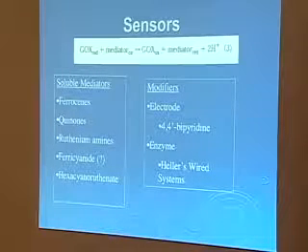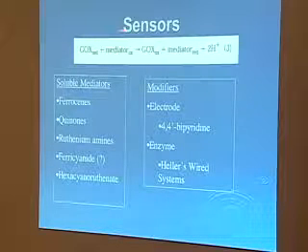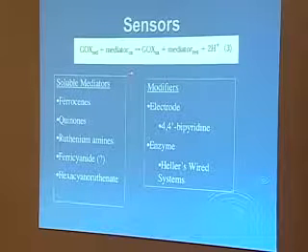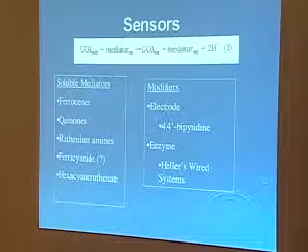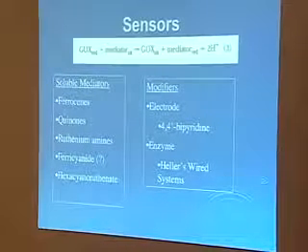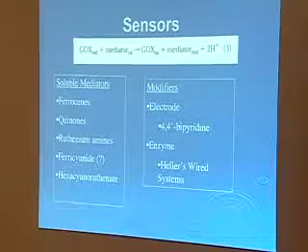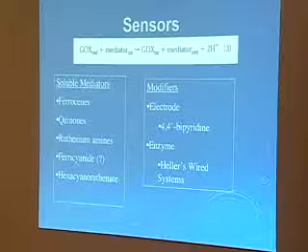So this idea is, instead of using oxygen to turn over the glucose oxidase, we use a redox mediator. And in doing that, we will simply collect the charge instead of looking for hydrogen peroxide as a product, or disappearance of a mediator spectroscopically. And by counting the charge, we can figure out how many times we've turned over this glucose oxidase, and hence how much glucose is around.